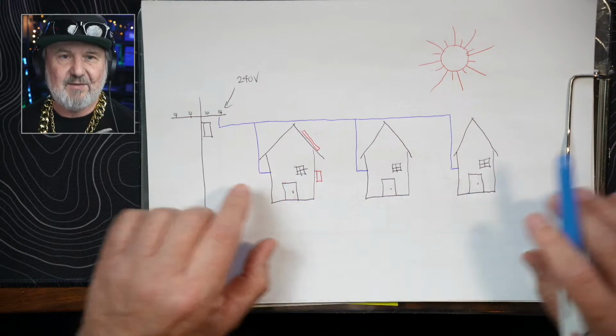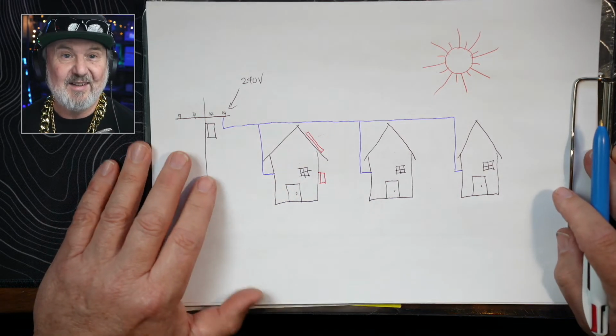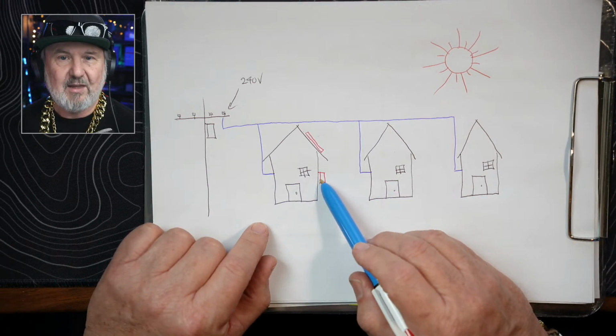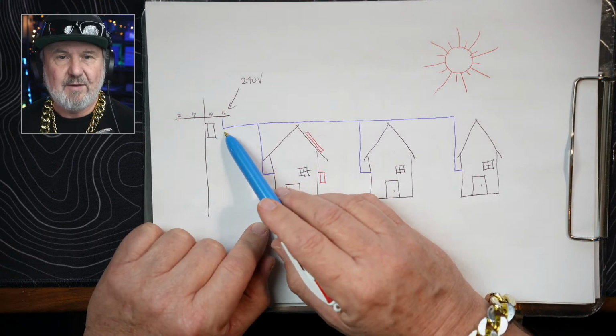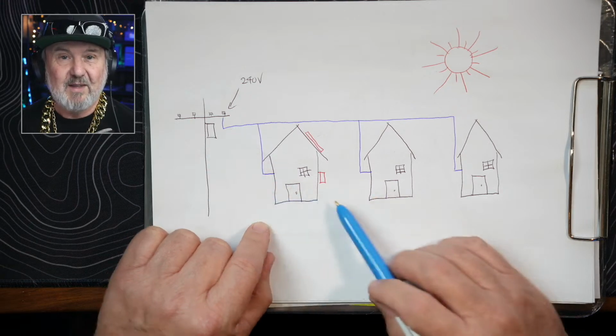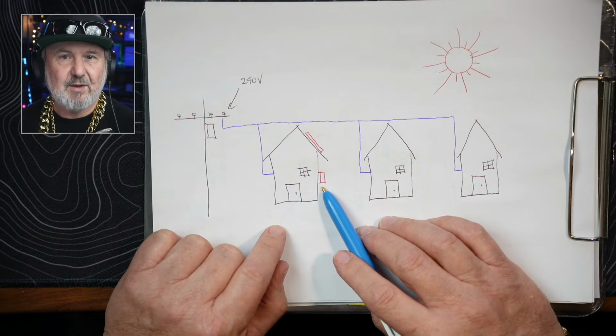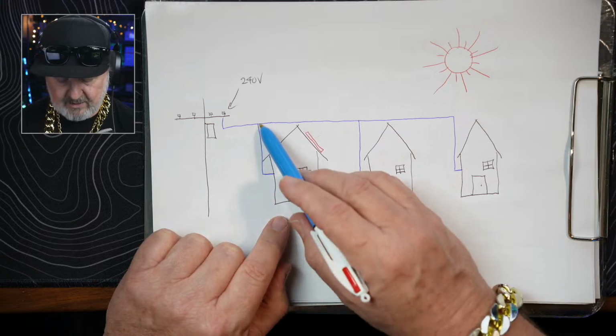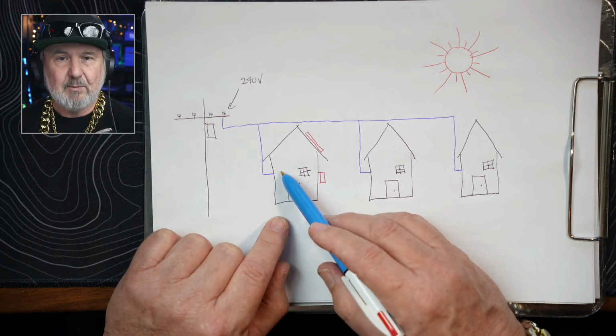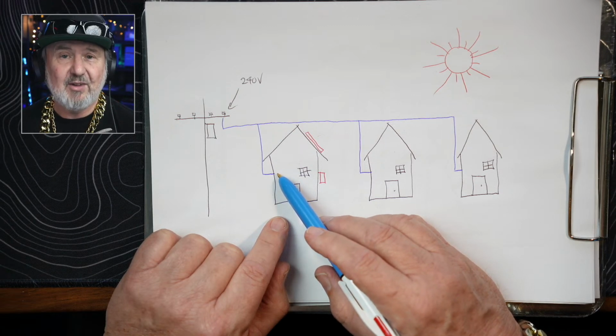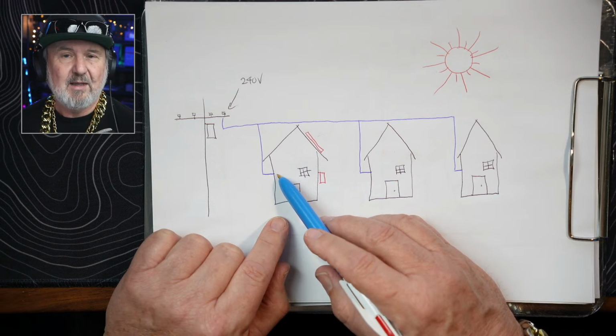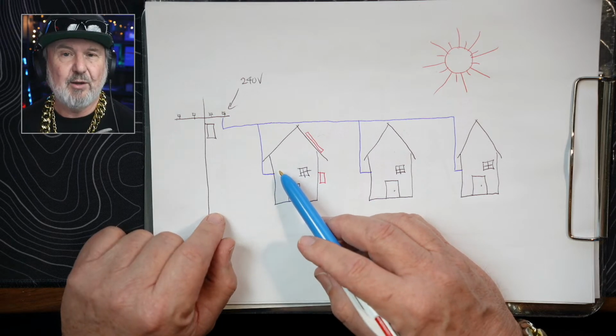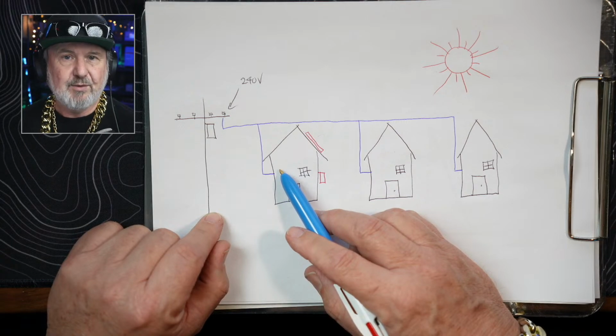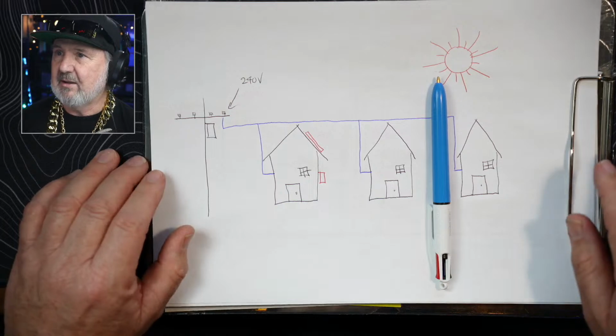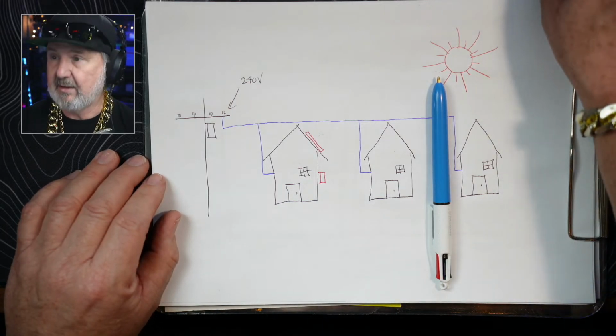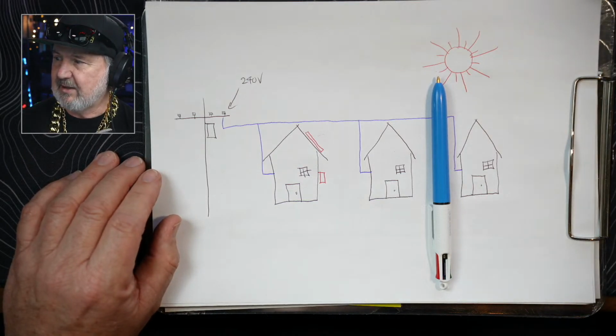Now, Ohm's law tells us that you actually have to have a higher potential at one end of a wire than the other in order for current to flow. So the voltage at the inverter's terminals has to be higher than over here to where it's going. So that's exactly what an inverter does. It slightly raises the voltage, and the amount of voltage rise based on power is all about the resistance, and it's impedance really, of this cable. And so the longer that cable is and the thinner that cable is, the more voltage rise you'll get across it for exactly the same amount of power being transmitted. So there's one thing to be aware of. Long, thin cables are a problem for voltage rise. But at this moment, we don't have a problem because, and I need to cut back to the example I had. Where is it now? From New Zealand standards and Australian standards.